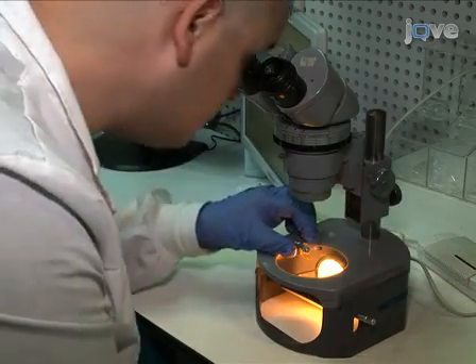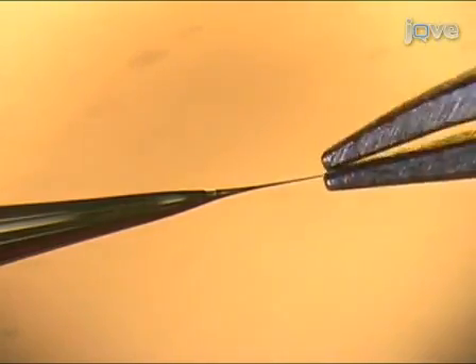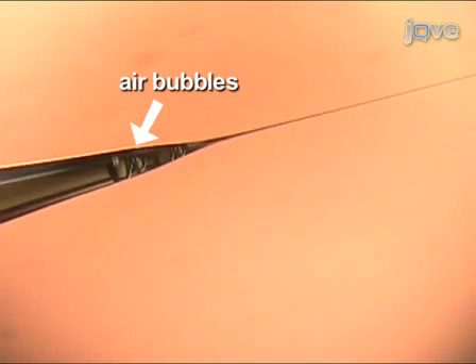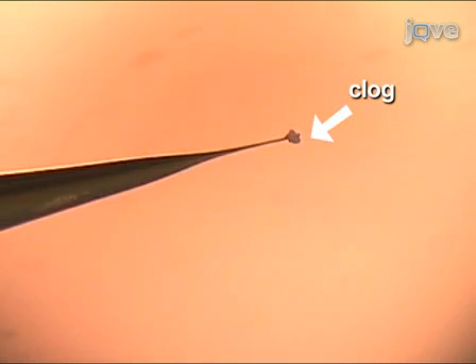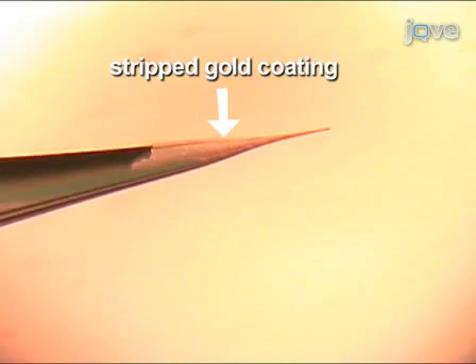Place the capillary under an optical microscope and use sharp AA-type tweezers to trim the tip. It is important to validate that there are no air bubbles within the capillary that could block the flow and that the capillary is not clogged. In addition, make sure that the gold coating is not stripped from the capillary. If so, replace the capillary or trim the tip and remove the uncoated section.